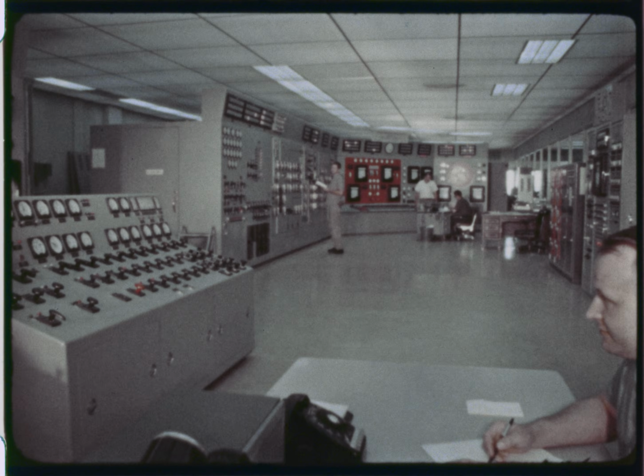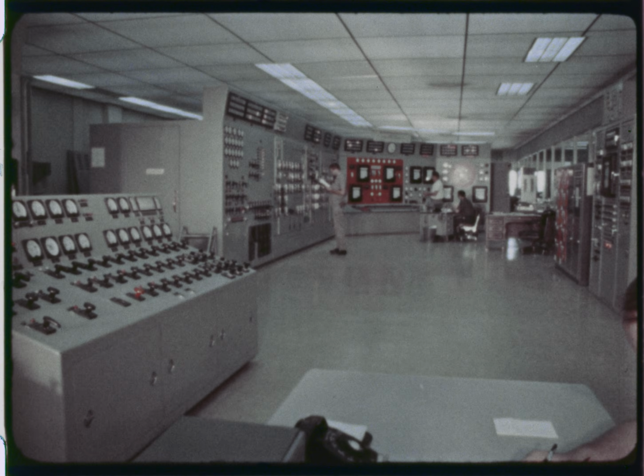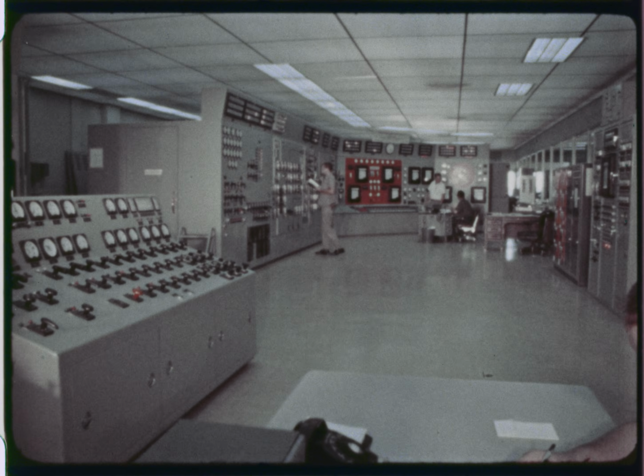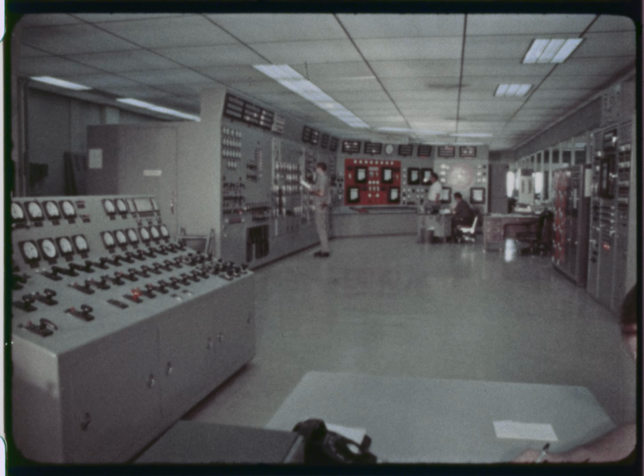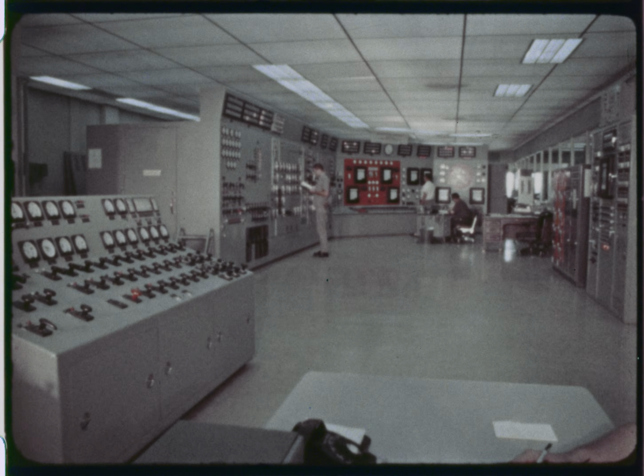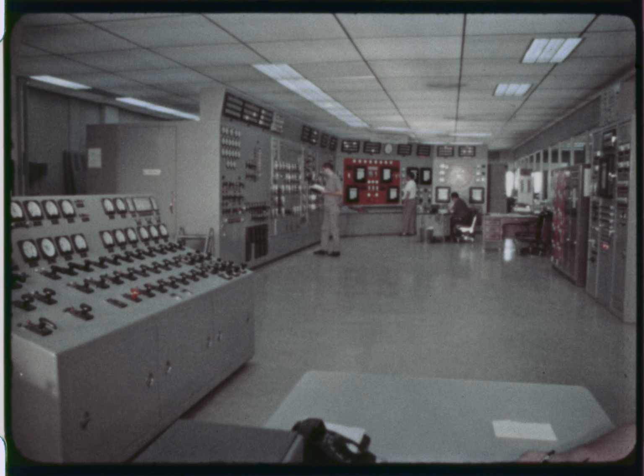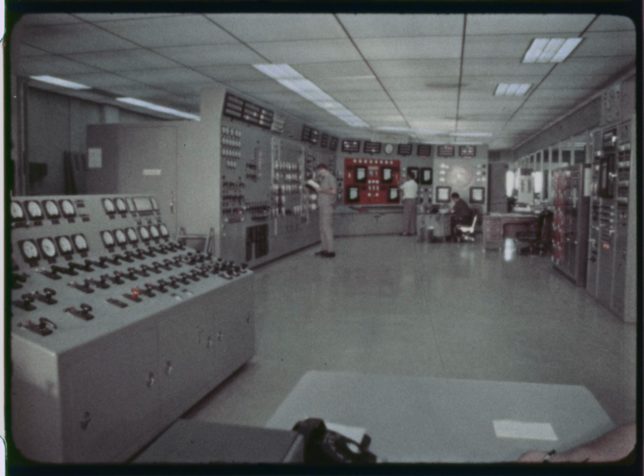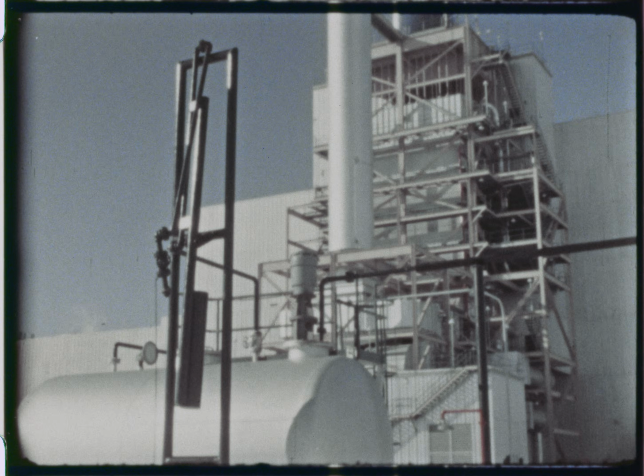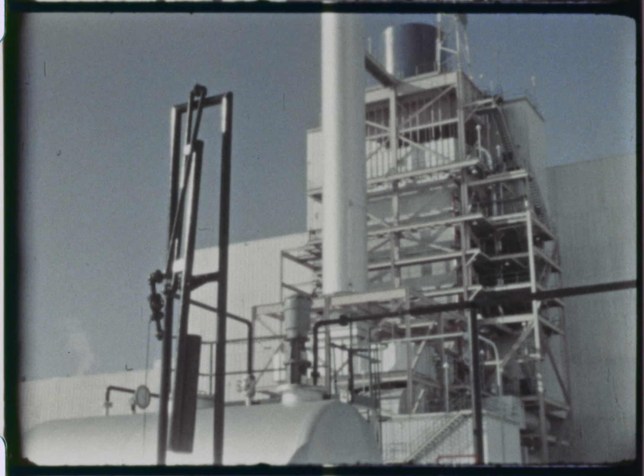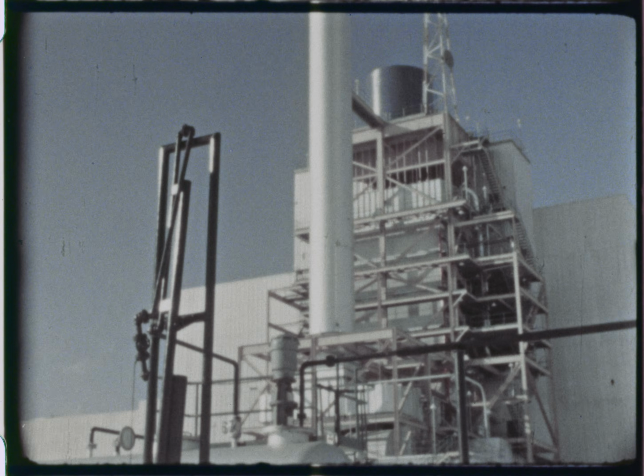The two facilities, conventional and nuclear, have centralized control, so integrated that the turbine generator can be operated automatically using either source of steam. After completion of the reactor test operation, it is planned to release the fossil fuel boiler from the system for use with a second generating unit which may be built later on the site.